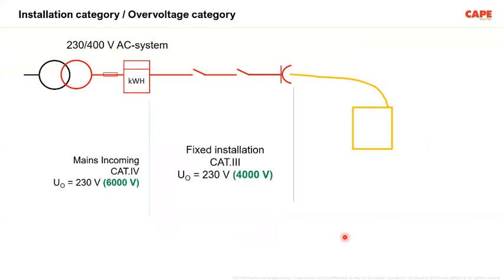Similarly, another important subject which is under the scope of the energy supplier, and which most of the time creates trouble in the consumer premise, is called installation category or overvoltage category. What it means is, you have the transformer, you have the meters, then you have the fixed part of the installation, then you have the connected apparatus.